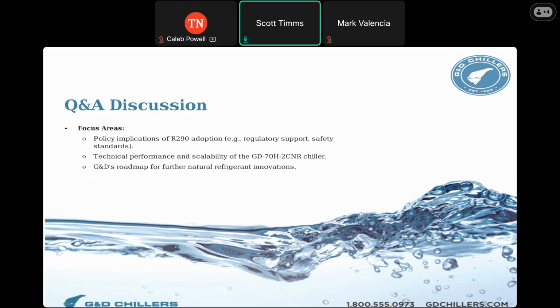The other situation where it makes a lot of sense is in a lot of wineries, where essentially you're fermenting for very short periods of time over the year. You're not fermenting year round for most wineries, and then you have barrel rooms that you need to keep conditioned. So during the summer, essentially you're not fermenting, so you can use your chiller to keep your barrel room at the temperature you want, since you're not really using it to ferment.